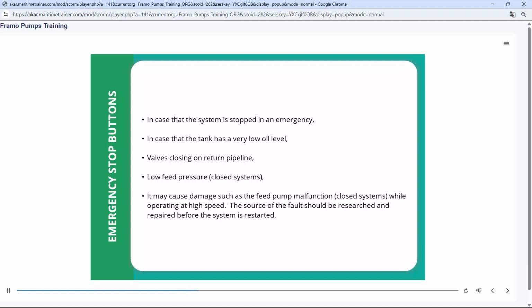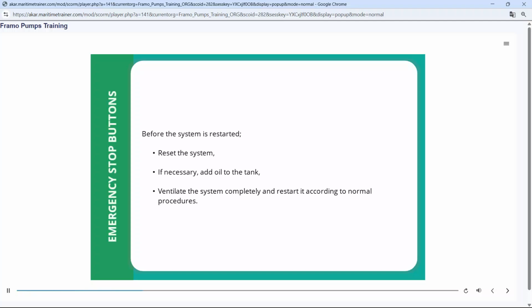Valves closing on the return pipeline. Low feed pressure. It may cause damage such as feed pump malfunction while operating at high speed. The source of the fault should be researched and repaired before the system is restarted. Reset the system. If necessary, add oil to the tank. Ventilate the system completely and restart it according to normal procedures.